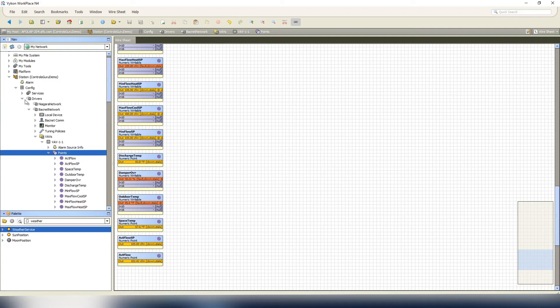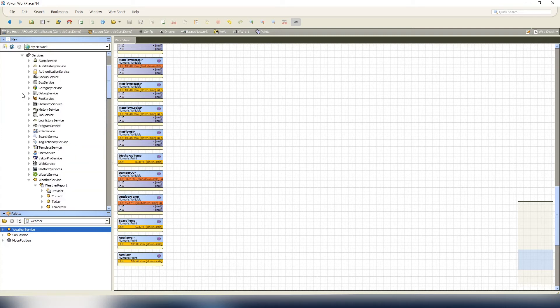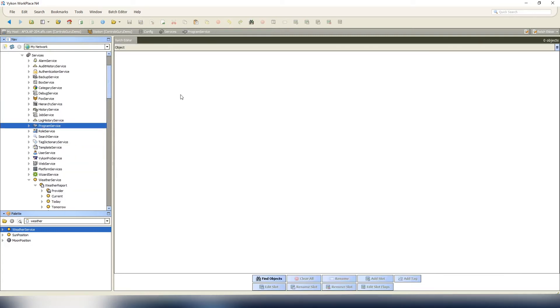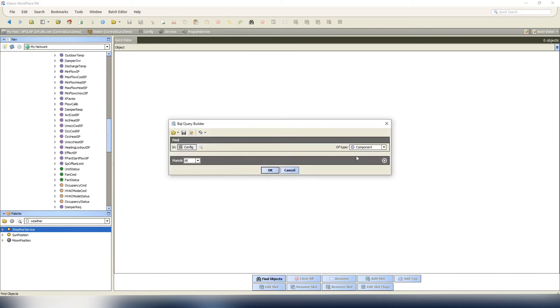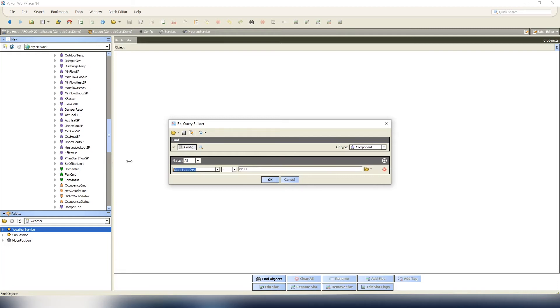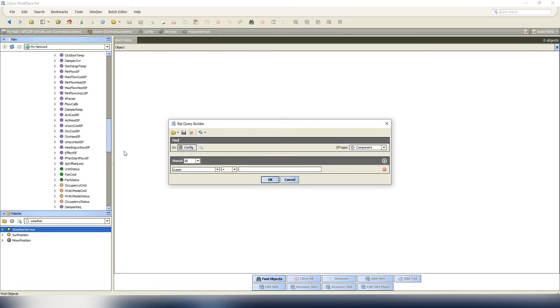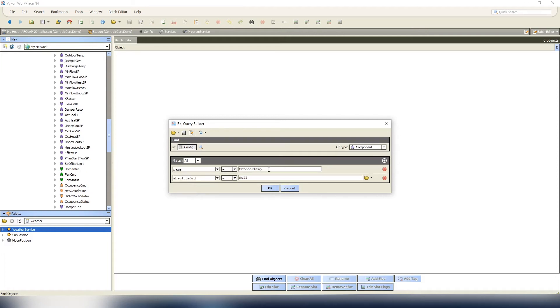Let me go ahead and show you how to do this. Let's open up your services, your program service. We're gonna do a find object. I've shown you how to do this in the past. What we're gonna look for is name equals - and again, this is case sensitive, so make sure you match the case to how it exactly appears in the points folder of your controller. Name equals outdoor temp.